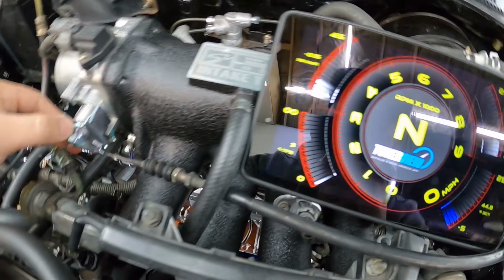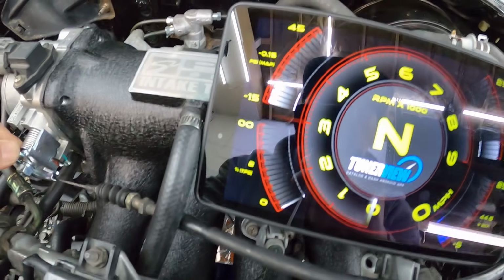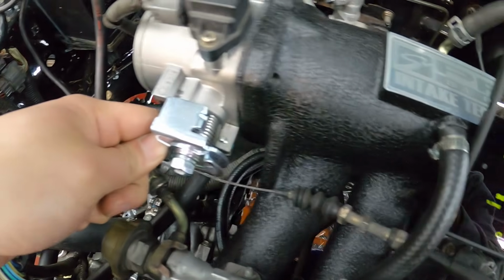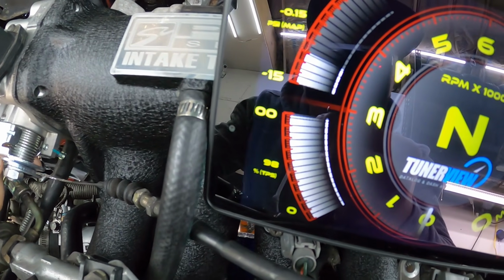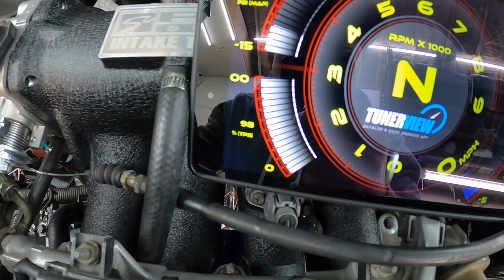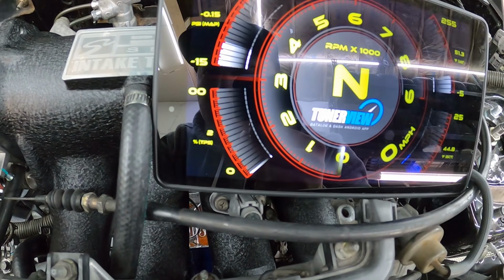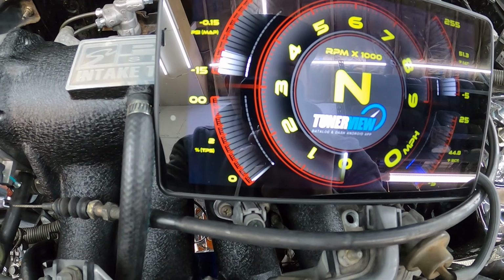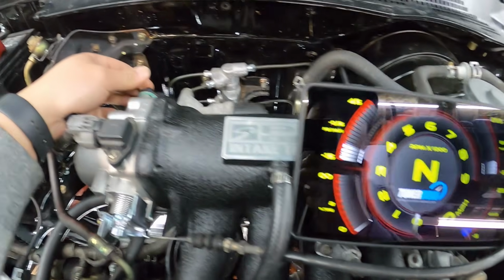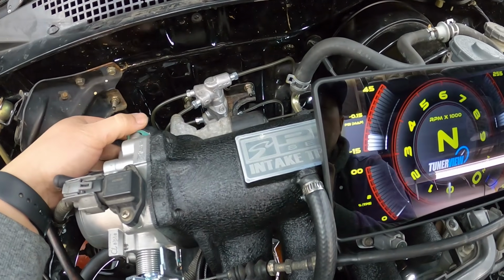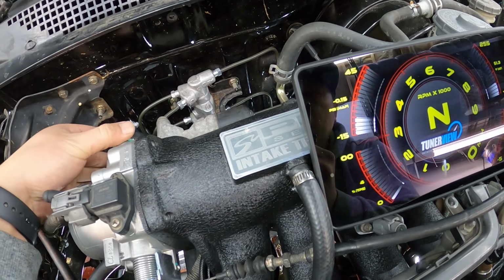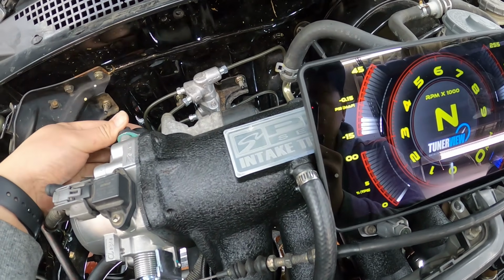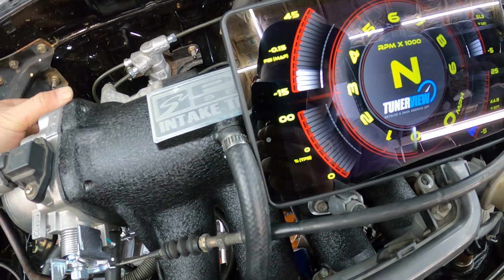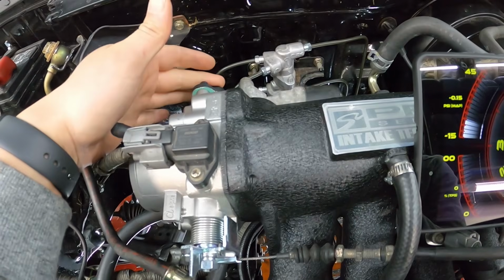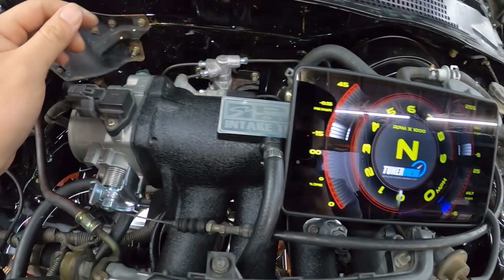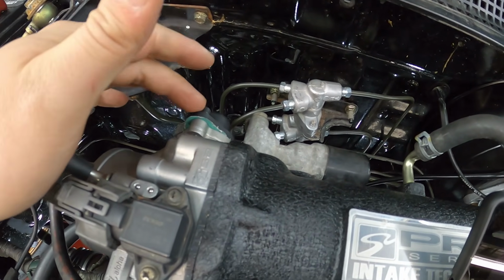When I hit the throttle, it changes. But if you look at the max, I'm fully maxed out, fully wide open throttle, but it's only reading 98%. That just means it's out of calibration. See, even now it's reading 2%, so we have to adjust it. But if you look over here, as I turn this, it's going to change the percentage on the gauge also. You got to move it until it says exactly 0% right on the edge, and then I'll tighten the screws for the TPS down.